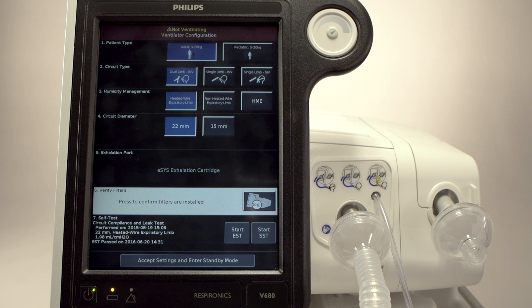This opens the Ventilator Configuration screen. For consistency and ease of use, when setting up either invasive or non-invasive ventilation, you will use this same screen. But, please note that only the settings applicable to your selected configuration are displayed. See what happens as we select different configurations.